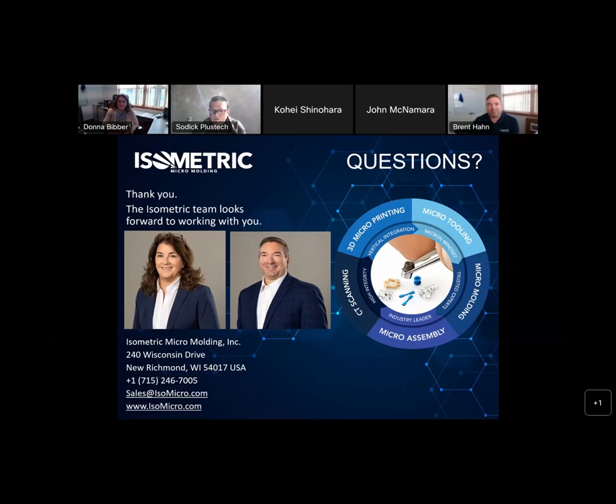Question: On average, how long does it take to qualify or validate a new product? Answer: For an implant it might be longer, since our customers take longer for OQ answers to come back. In general, for a medical device, our validation is somewhere around 10 weeks or so, maybe less in some cases. Mold build on average is 8 to 10 weeks right now — right after COVID it was higher, but it's settled back. So roughly 8 to 10 weeks to build a mold and a similar timeline to validate.